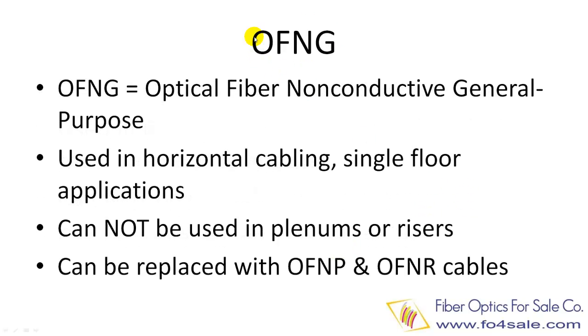The next level is called OFNG cables, where G stands for general purpose. OFNG cables are used for general purpose areas, such as horizontal cabling and single floor applications. OFNG cannot be used in plenum or riser areas, but OFNP and OFNR cables can be used as a substitute for OFNG cables. In most cases, installers use OFNR riser rated cables for all non-plenum areas, because the cost difference between OFNR and OFNG is so little that it doesn't make sense to use OFNG cables at all.